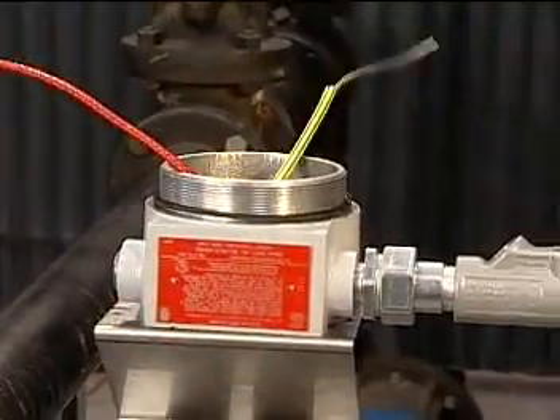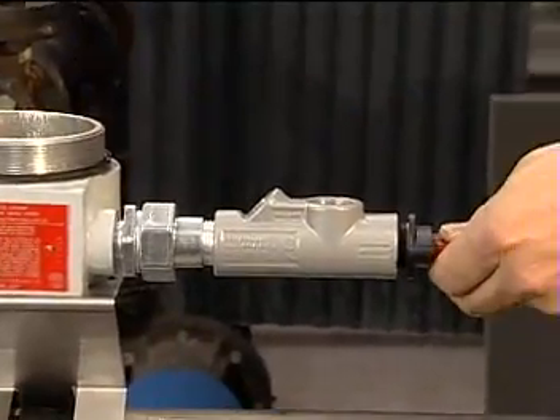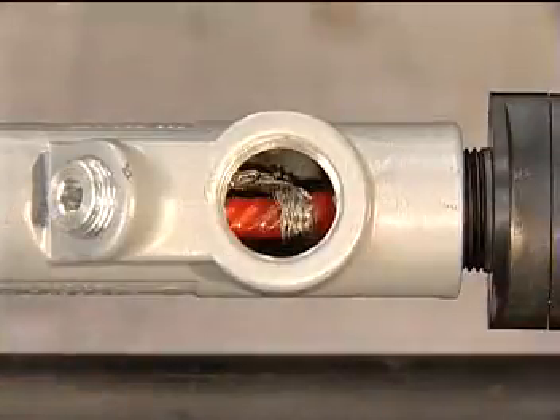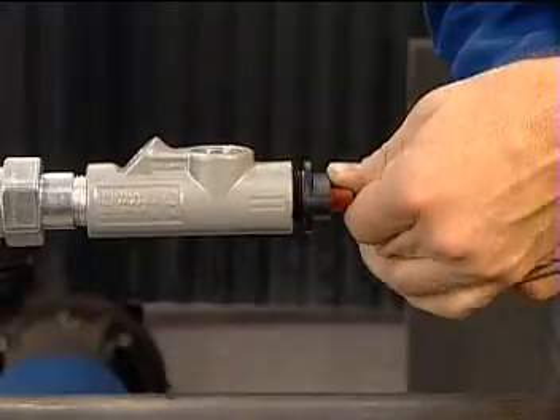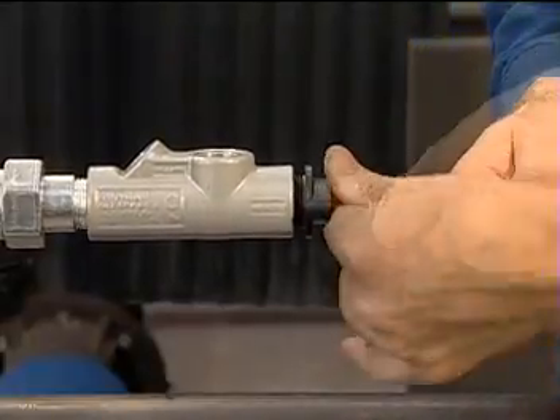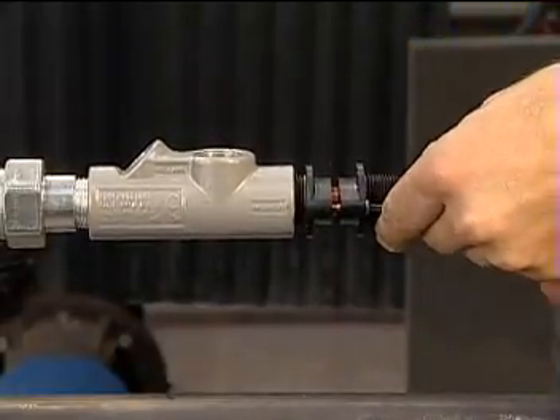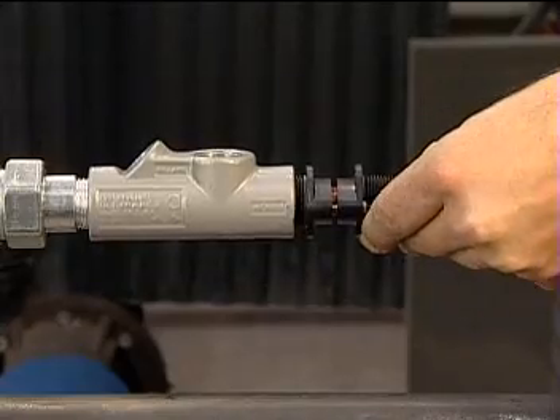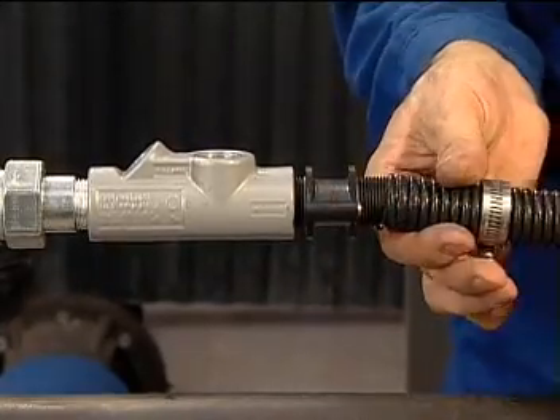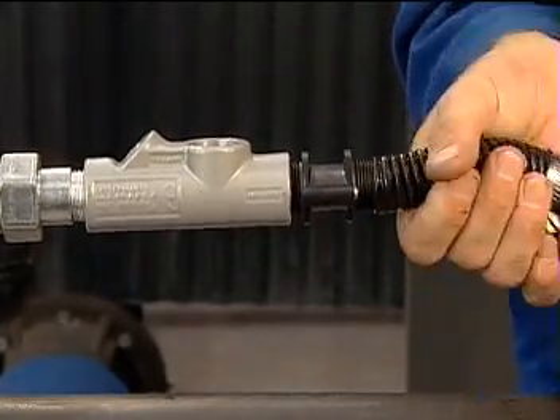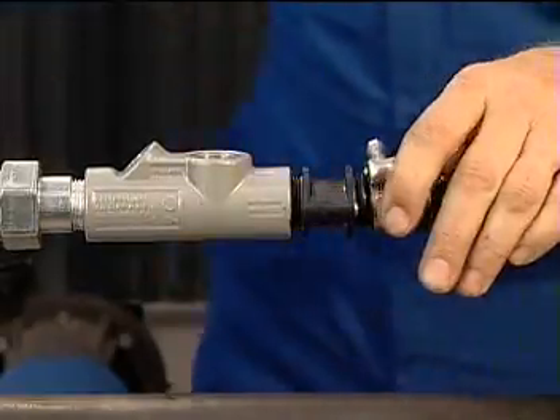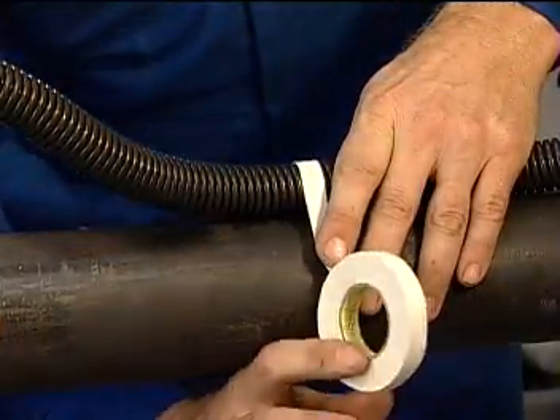Pull the cable into the junction box so the braid pigtail is centered in the large opening of the sealing fitting. Position the grommet in the cavity and tighten the compression gland with the screws provided. Be careful not to change the position of the cable in the sealing fitting. Screw the corrugated tubing onto the gland and tighten it with the clamp. Then, tape the tubing to the pipe.